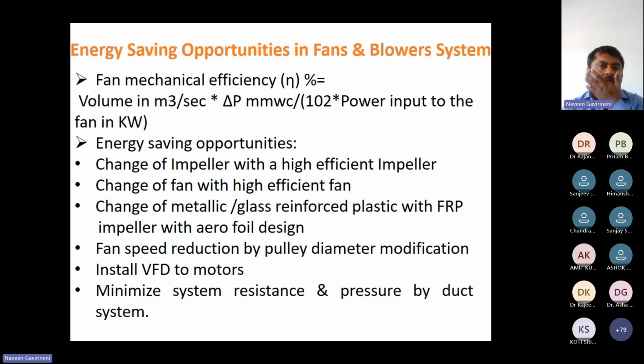So this is the energy saving opportunity for the fan and blower system. Fan mechanical efficiency, I already explained. Energy saving by change of impeller, mainly because the flow we get is from the impeller only. So change of impeller, a fan with high efficiency. There is also the impeller material, metallic or glass reinforced plastic, used in olden days. Now they have all been converted to FRP impellers only. But with FRP impellers we must be very cautious about high temperature and so on, because there is a chance of damaging the FRP.